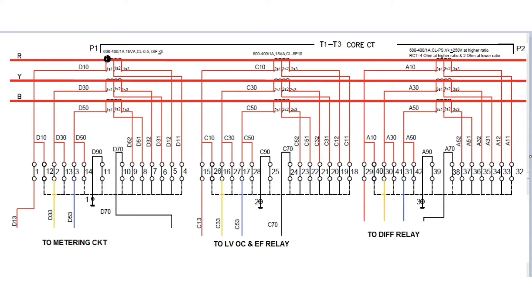For the metering core, the CT specification has two ratios: one is 600/1 and another is 400/1. The CT burden rated is 15VA, class is 0.5, and instrument security factor is less than or equal to 5. That is the specification of the metering core CT.